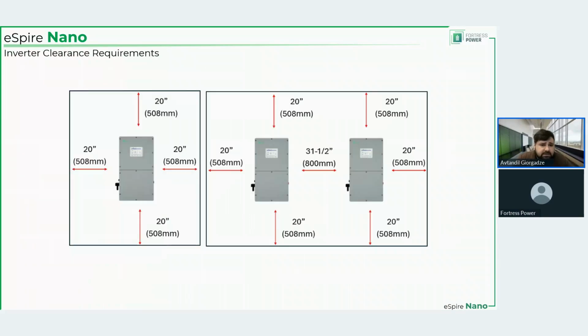Next, clearances around the inverters. It should have 20 inches of clearance in every direction around it, right? Top, bottom, left, right, unless it has another inverter on its side. So the distance between the inverters is even greater than 20 inches. That is actually 31 and a half inches, which comes down to 800 millimeters, which is 0.8 meters, almost 0.8 yards. The reason behind this bigger distance between them than 20 inches is, again, because they are air-cooled. They create a kind of layer of warmer air around them, and we don't want that overlapping, and we want to avoid that as much as possible. So these are the numbers to follow.